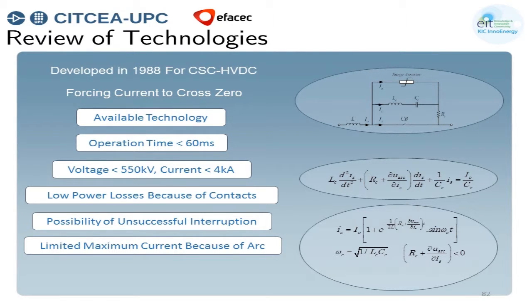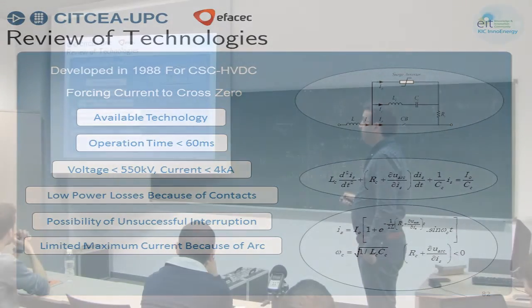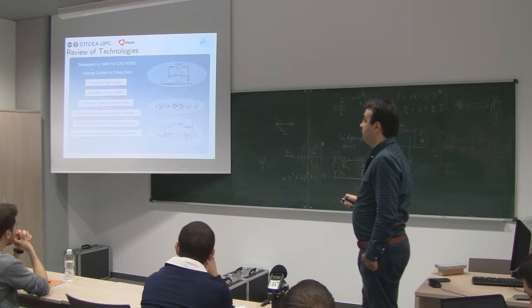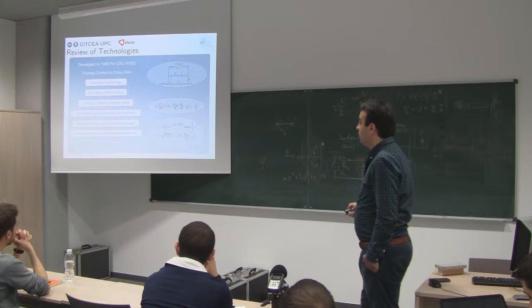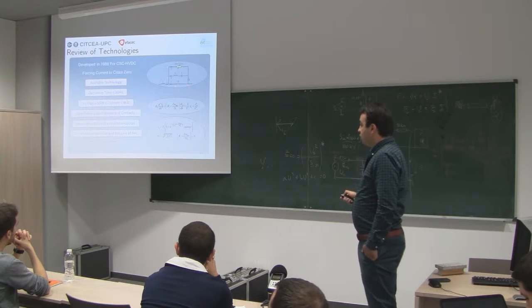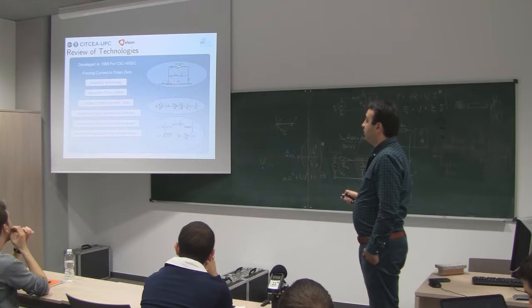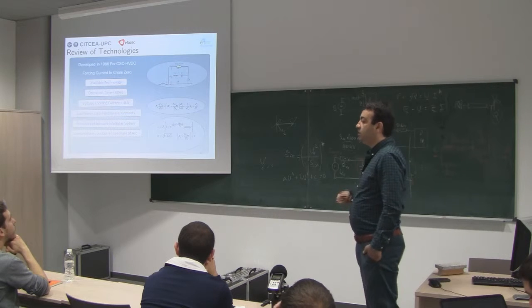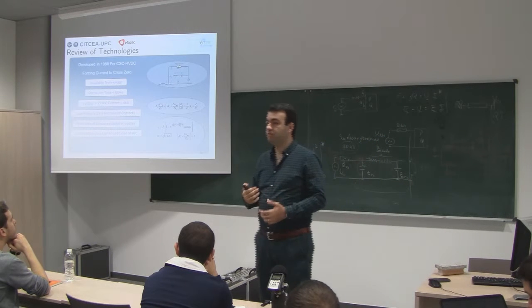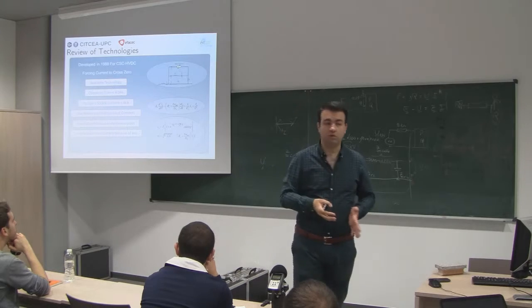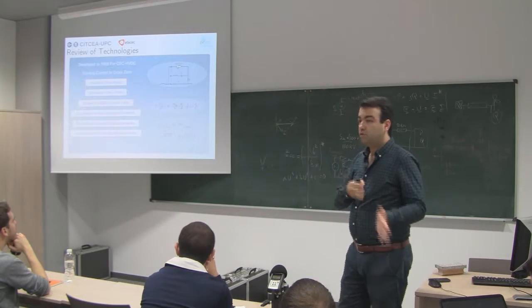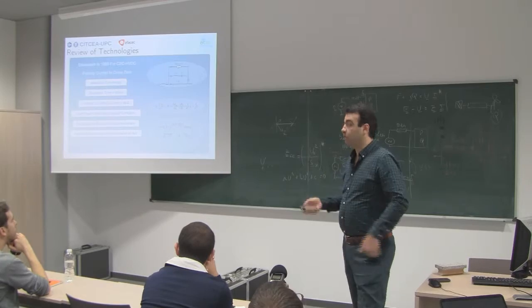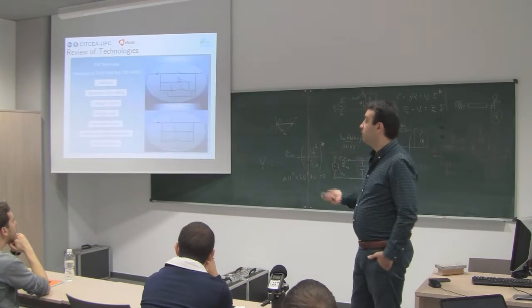It's ready for quite high voltage and good current, 4K amps. It has a low power loss because you have mainly a mechanical breaker here. So this is a metallic contact, so you have low power losses here. And the principle of operation is opening this breaker and imposing an oscillating current, which is opposing the fault current and pushing the summation of the fault current and the opposing current to cross the zero. And after that, we can quench the current.